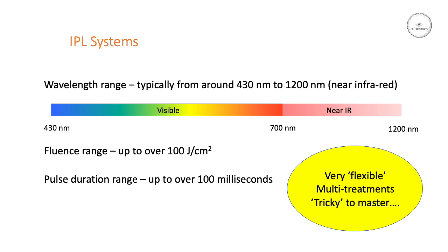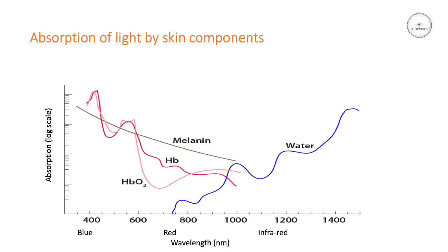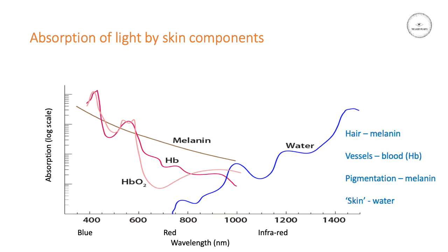But it also makes it trickier to master since you have much more choice compared to typical laser systems. So let's look at the absorption characteristics for various chromophores in the skin. Here we can see the absorption curves for water, melanin, deoxyhemoglobin and oxyhemoglobin, and what this tells us is how well these chromophores absorb across the different colours of light at different wavelengths. Melanin absorbs pretty strongly down at the blue end of the spectrum, but it decreases as the wavelength increases up to around 1000 nanometers, where it absorbs much less strongly than at the blue end of the spectrum.